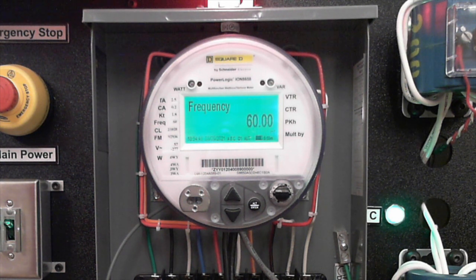The harmonics display goes up to the 63rd, and it's just using the 1 second average. It's not using the 1024 samples per cycle waveforms to calculate your harmonics on that page. But it's just to get a quick overview of your lower order harmonics.